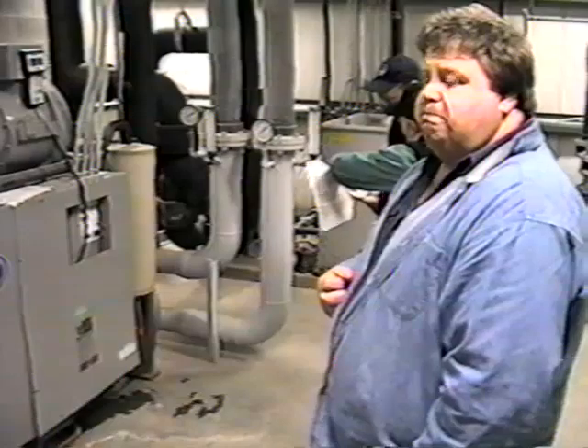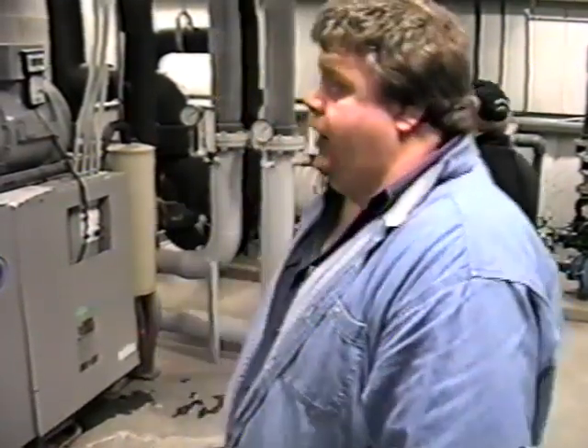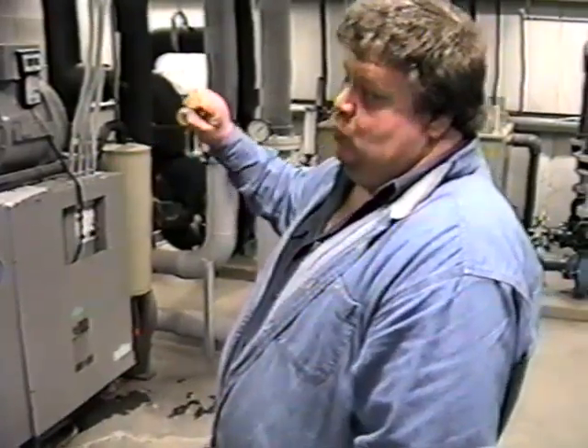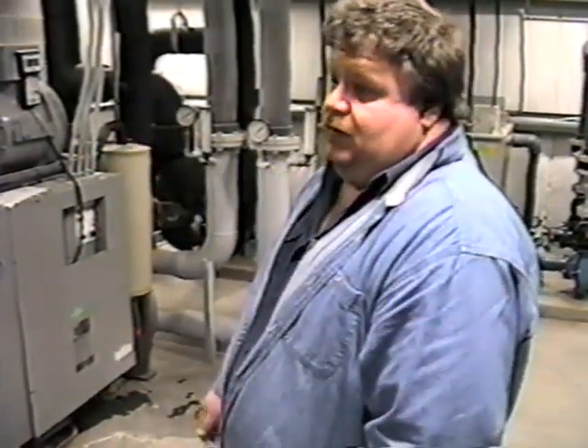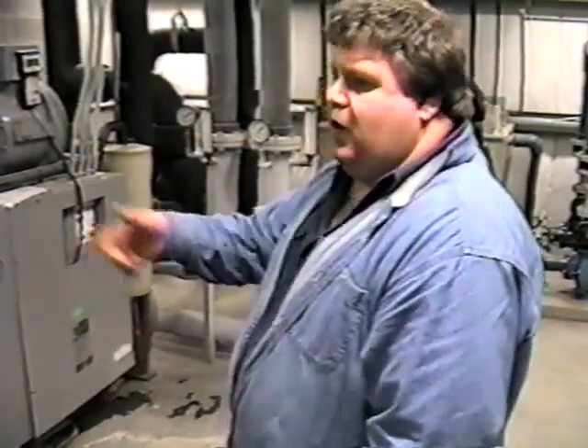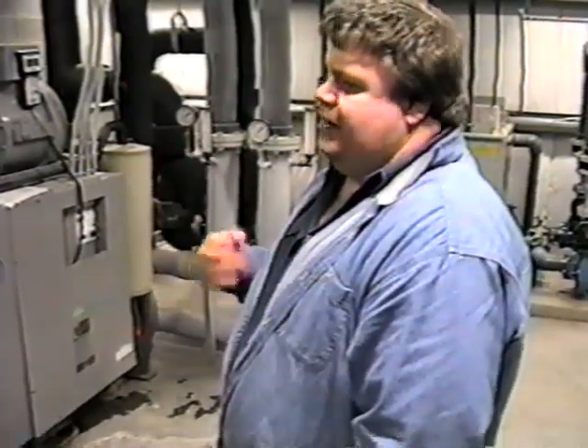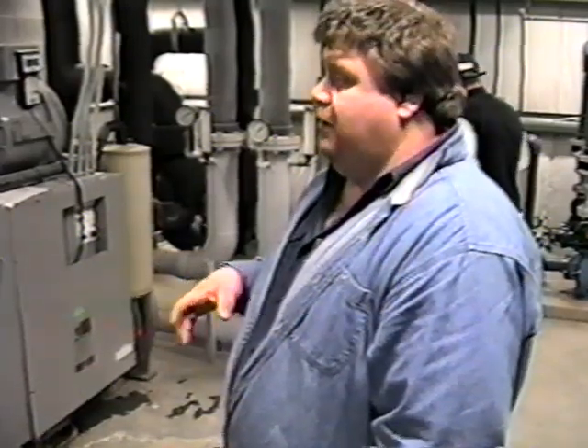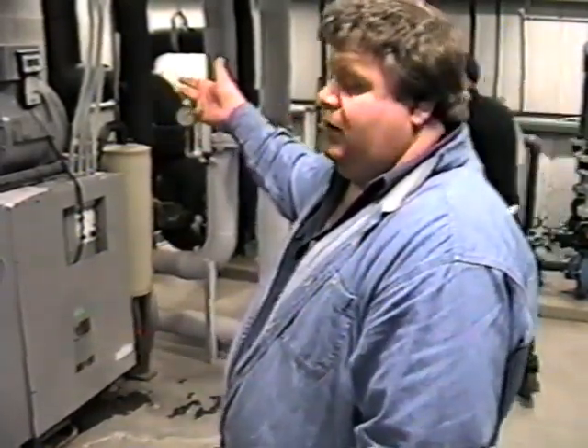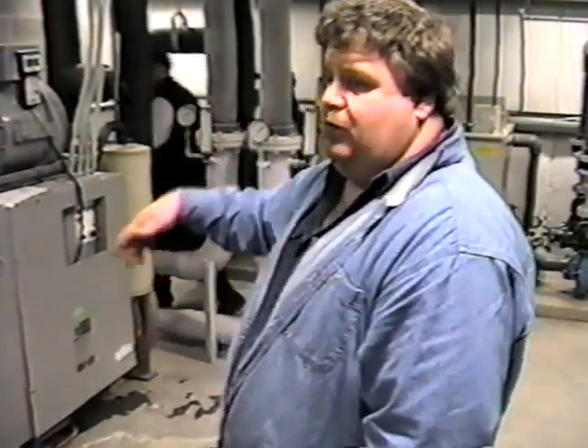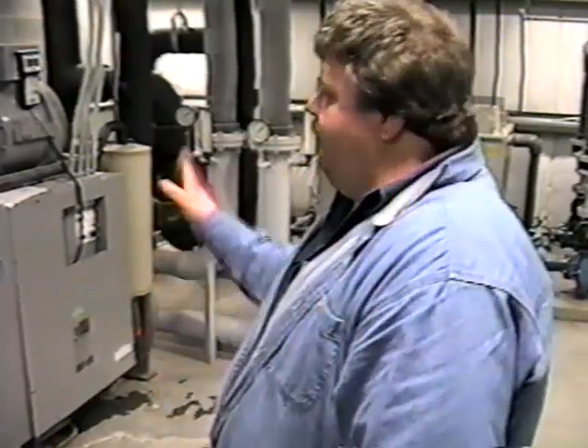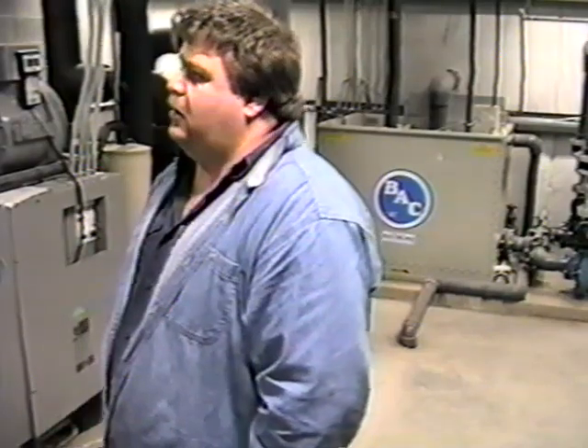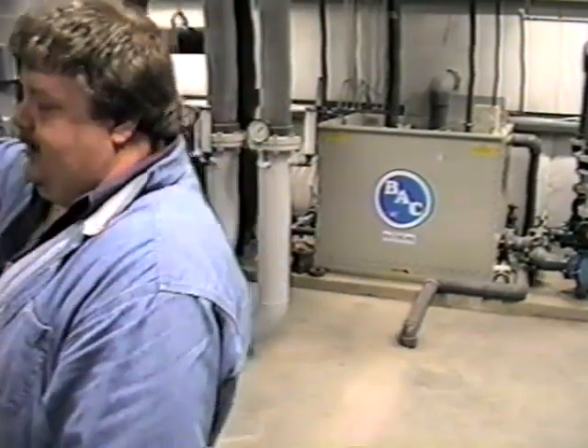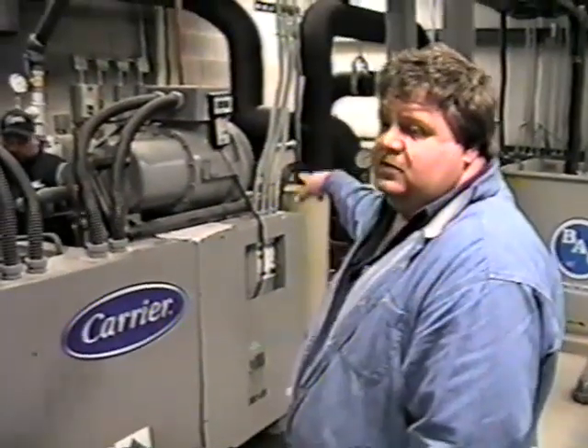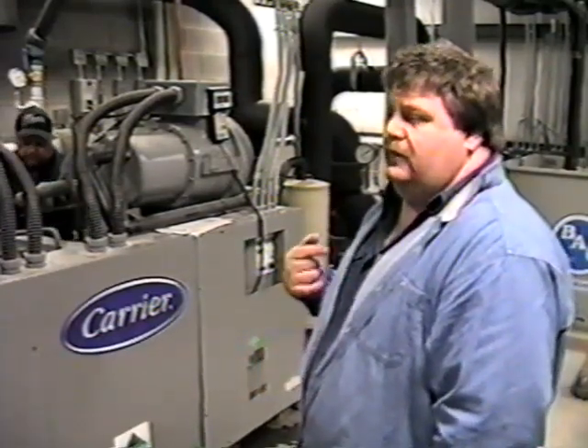But any changes made over here, as far as ice temperature or whatever, we're not doing any adjustments there, right? Right. Once this is set, we should be able to just leave this machine alone forever, really. As we were talking earlier, he was going through the parameters and stuff. That's all stuff that you guys really don't need to be dealing with. All you need is to be able to scan the temperatures and pressures, and if by chance you need to go to the bypass, how to do the set point. Other than that, you really don't need to be getting into the machine here. A lot of it's going to be strictly on this screen, and then on some of the gauges. And like I say, we can go through and make up a list of the important gauges.